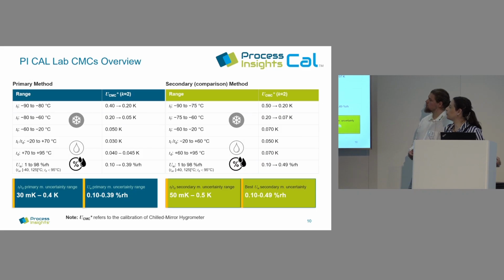So just to give you a quick overview of our measurement uncertainty. This is the example for the calibration of chilled mirror hygrometers. Of course, if you are using a different hygrometer for relative humidity, then you have higher values. But for the primary values, we are able to achieve 30 millikelvin up to 0.4 Kelvin in the dew and frost, and humidity 0.10 to 0.39. So this is our best method, the primary method, direct and traceable to the SI units.